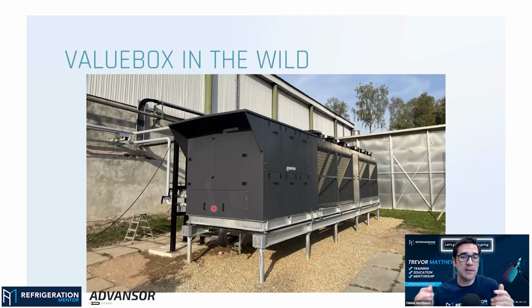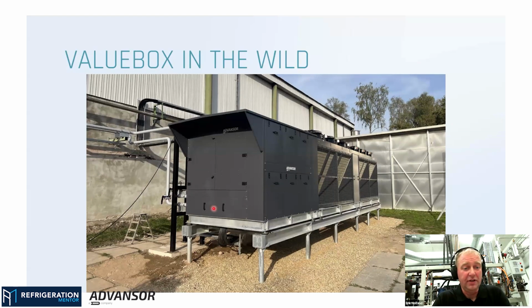Yeah. Okay. So that's great. So now the contractor got it. They built the stands, they built the French drain, they pulled the electrical, got the right power there, whatever the voltage is, depending on where you're at in the world, it's going to be a different voltage. And then they get the supply in and the supply out of whatever the process is. Yeah, that's basically it. And then what he has to do is of course make sure that his supply water is balanced to the calculation for the unit. Because we have been quoting a system that can deliver so many kilowatts at these temperatures at this flow. So if you don't have the right flow, you don't have the right temperatures, and it is quite difficult to adjust everything into a working system, because everything has been dimensioned for the quoted values.